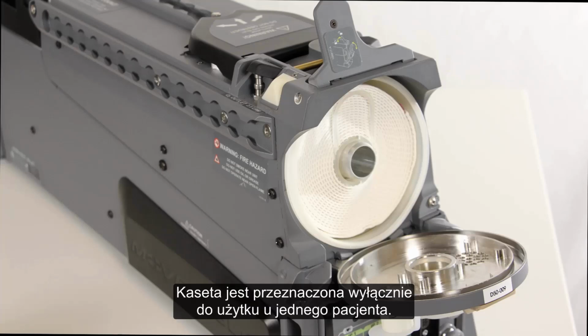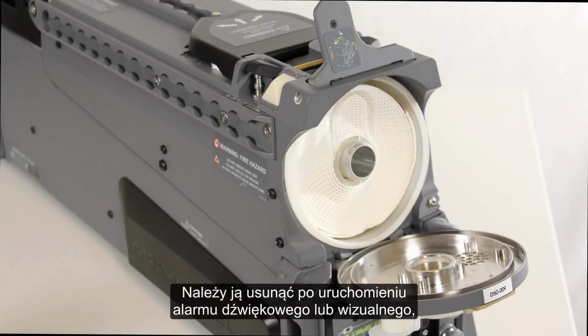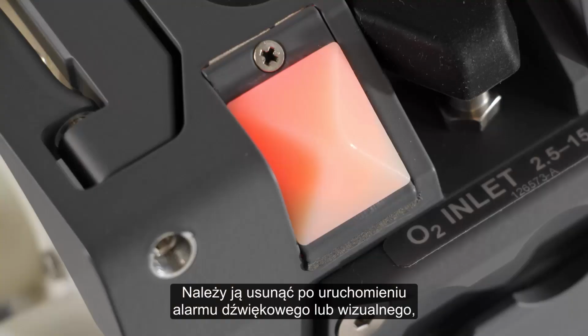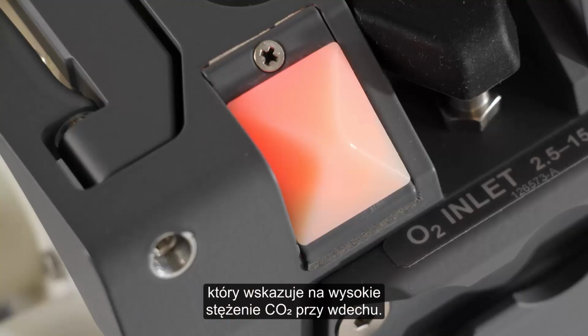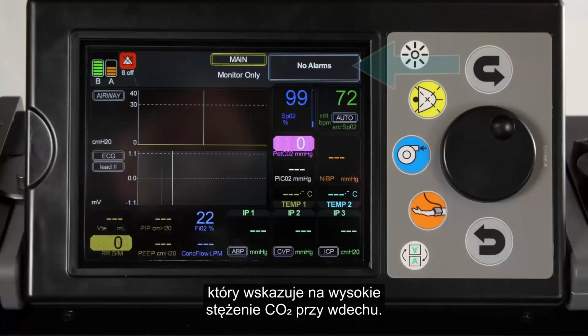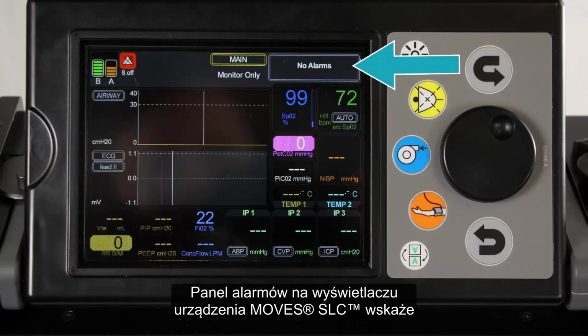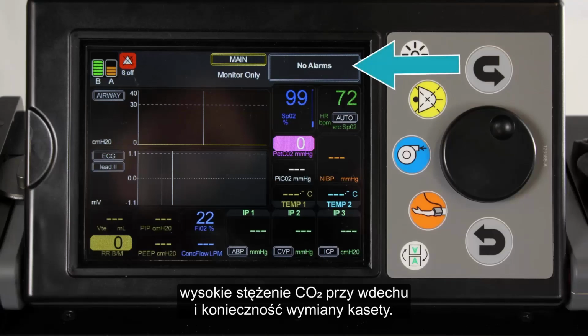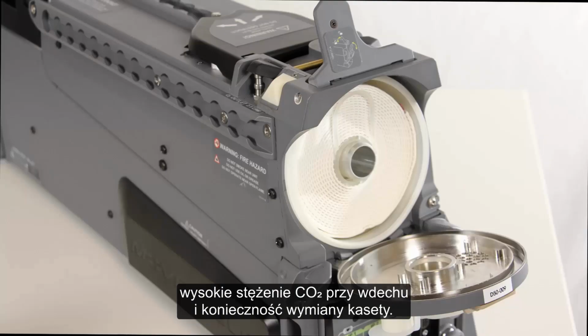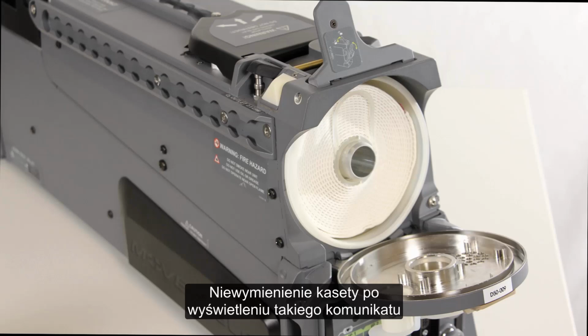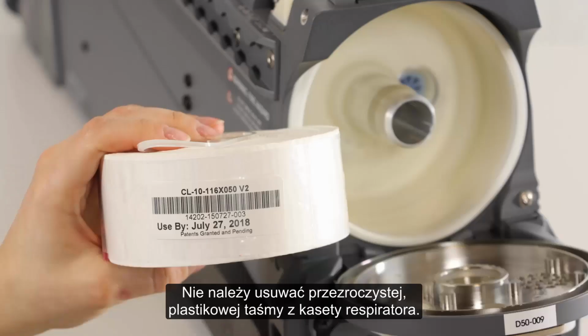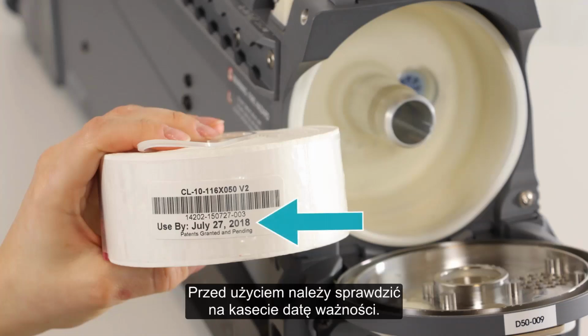The cartridge is also for single patient use only. It should be discarded when an audible or visual alarm is triggered, indicating a high level of CO2 on inspiration. The alarm panel on the Moves SLC display will indicate "Inspired CO2 high, change cartridge." Failure to change the cartridge when prompted will lead to inadequate ventilation for the patient. Do not remove the clear plastic binding on the ventilator cartridge. Always check the expiry date on the cartridge before use.